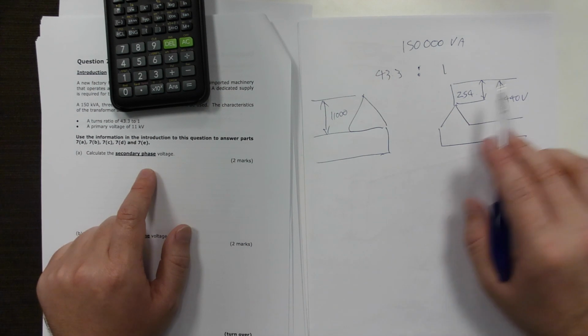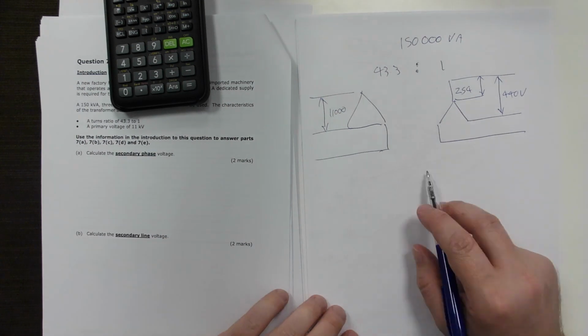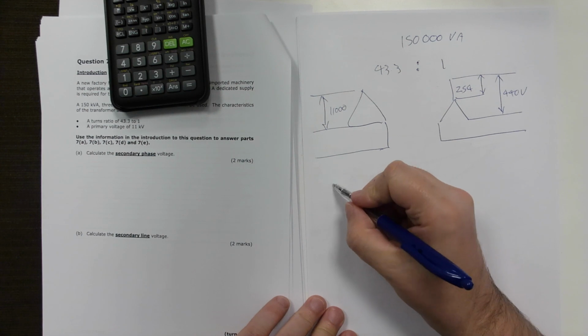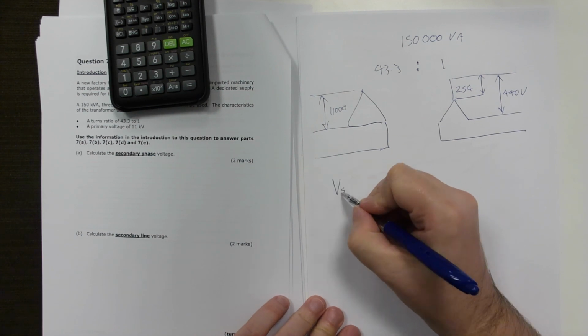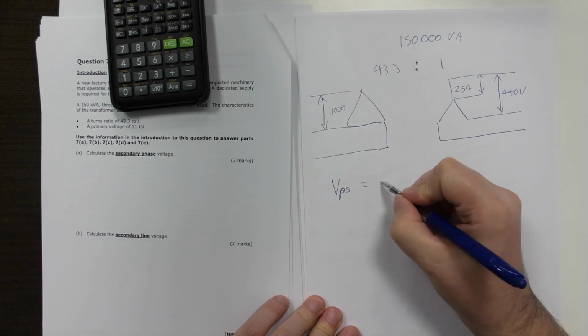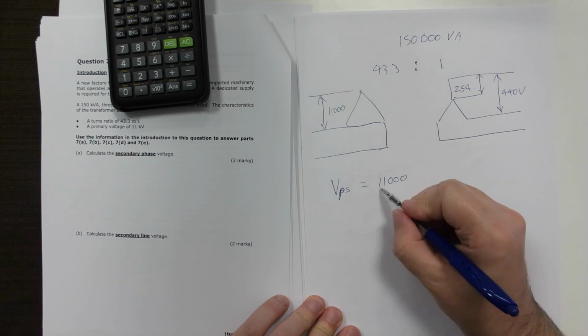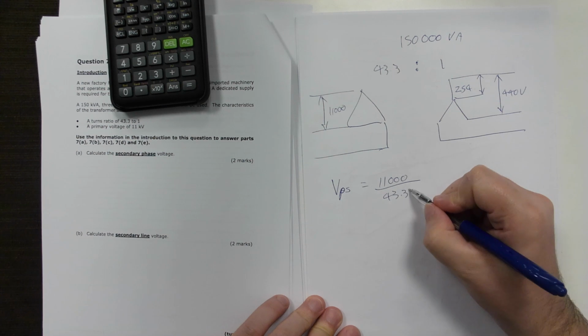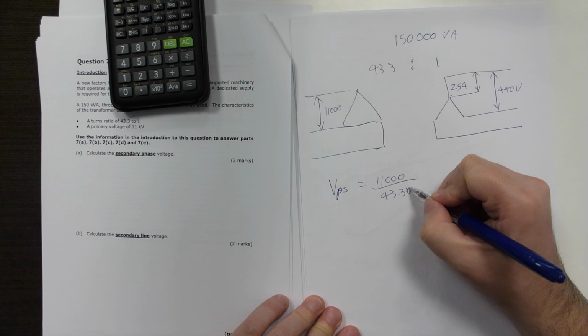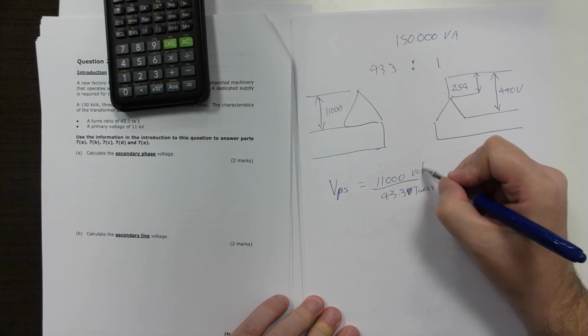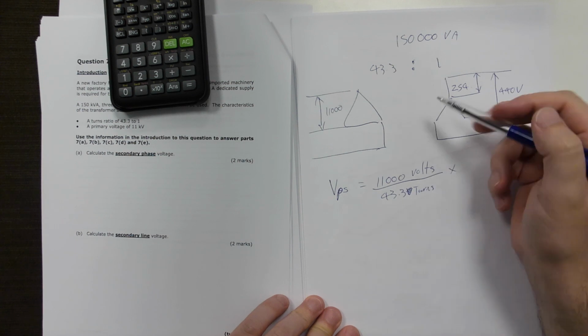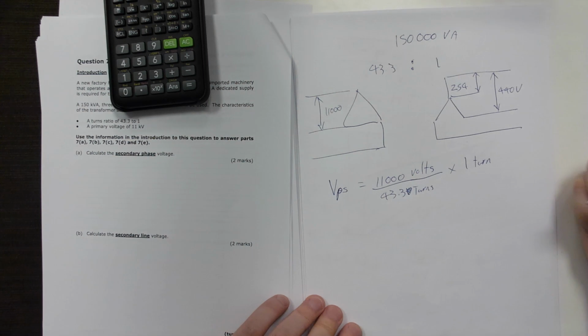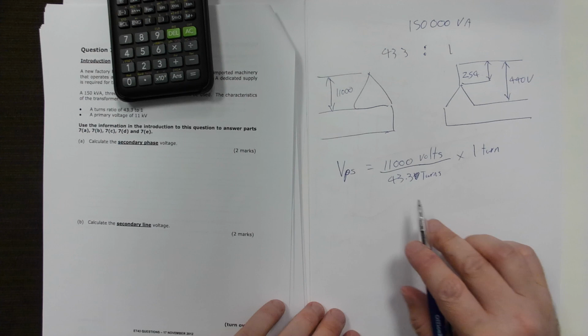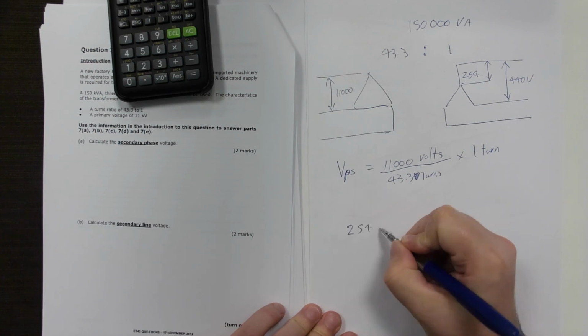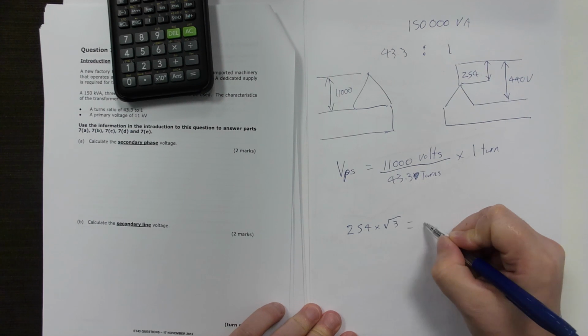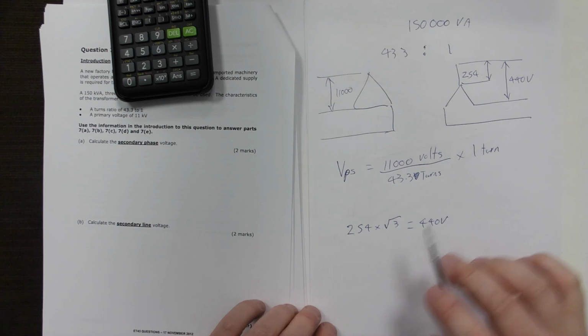So calculate the secondary phase voltage. We now know that that is our 254 volts, and our calculation for that is V phase secondary equals 11,000 volts over 43.3 turns, so turns and then volts. And then we would multiply that by the turns on this side, so one turn, if it was a different ratio. Next, thereafter, the secondary line voltage. For that one, it is simply 254 times by the square root of 3, which equals 440 volts. So that's our answer to question 2.